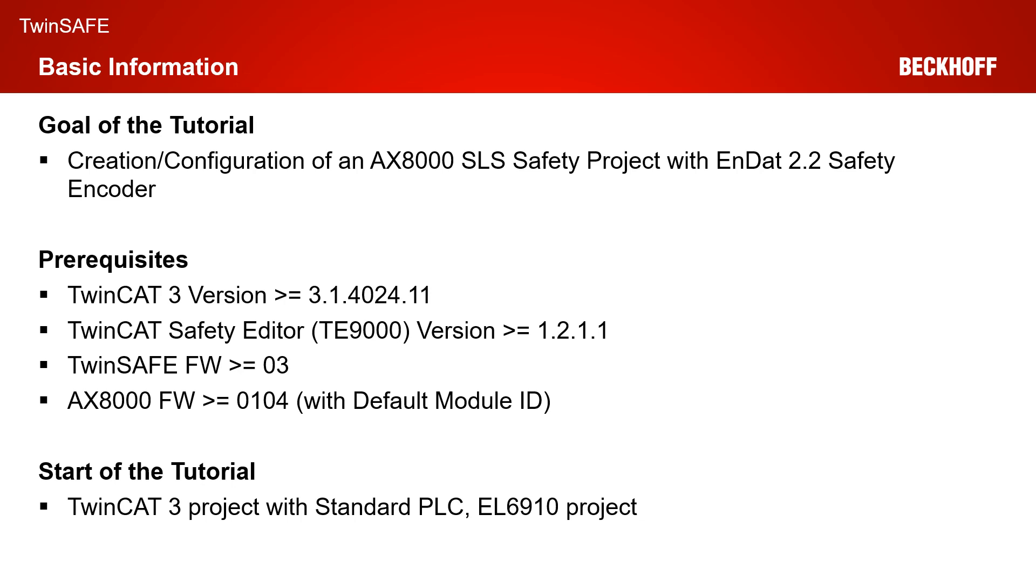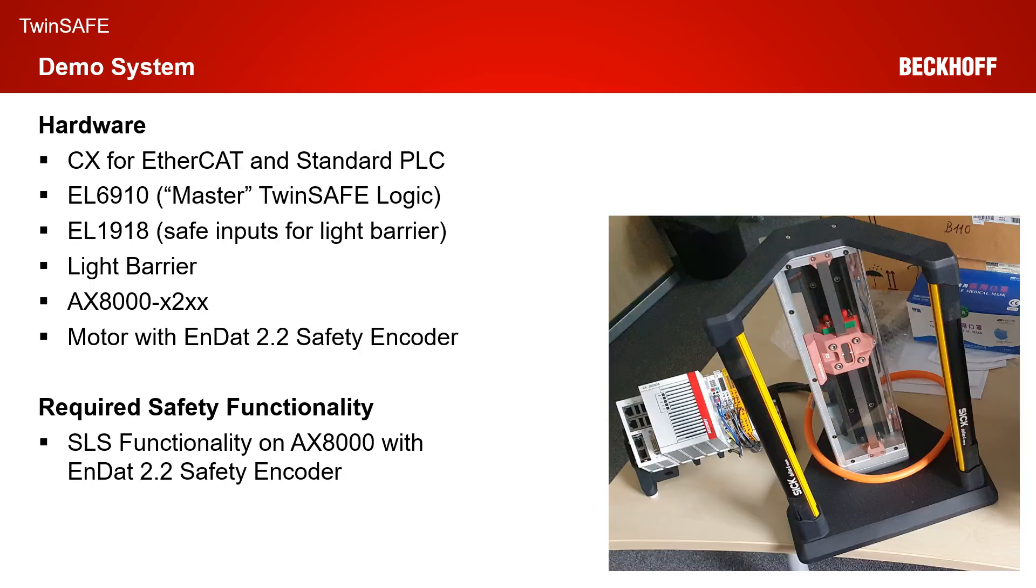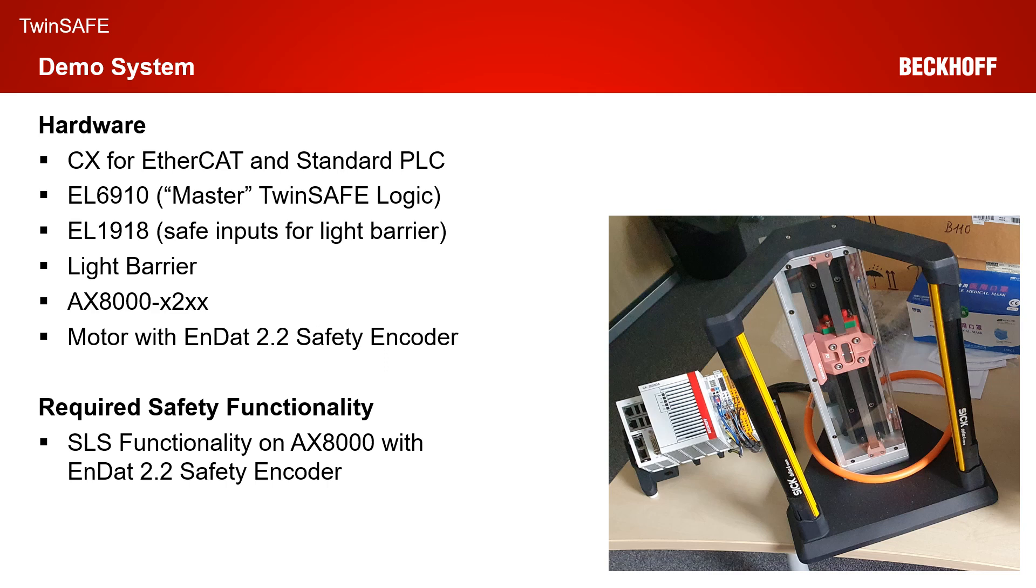The start of our tutorial today is a complete TwinCAT 3 solution with I/O configuration, a standard PLC and an EL6910 project which our AX8000 should communicate with. Our hardware consists of a CX for the EtherCAT communication and a standard PLC. We have an EL6910 as TwinSafe master logic which is communicating to the EL1918 where a light barrier is connected to.